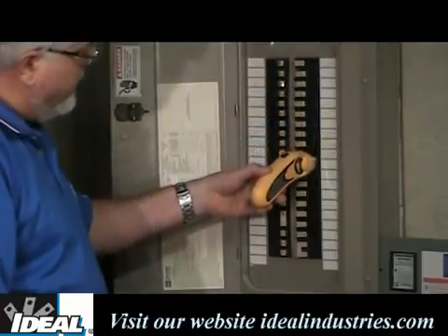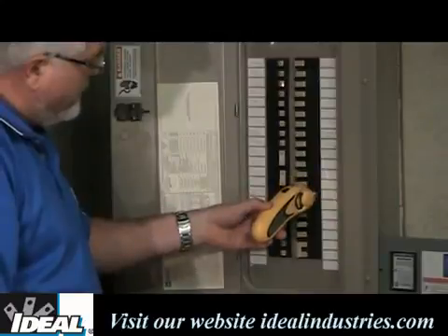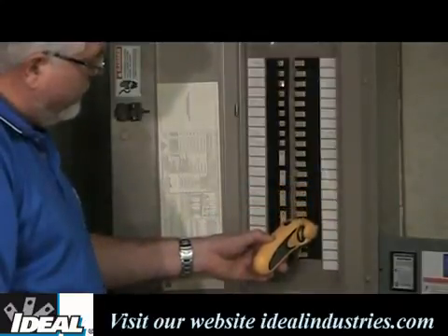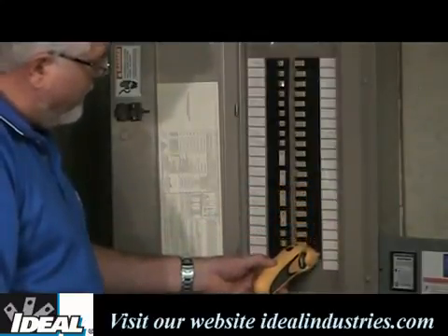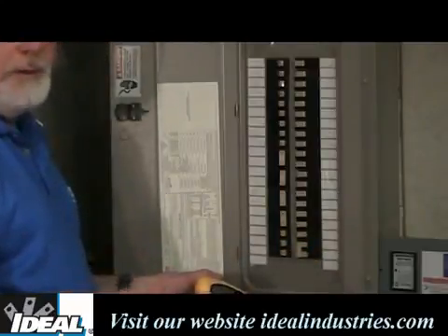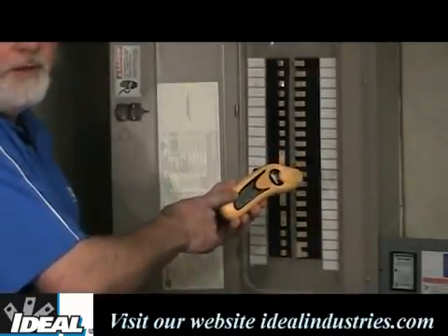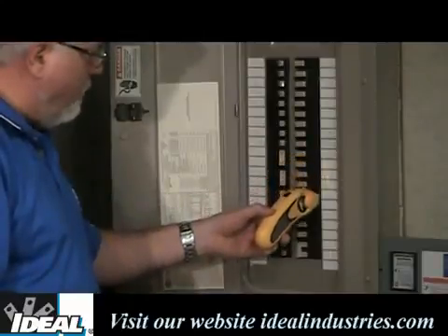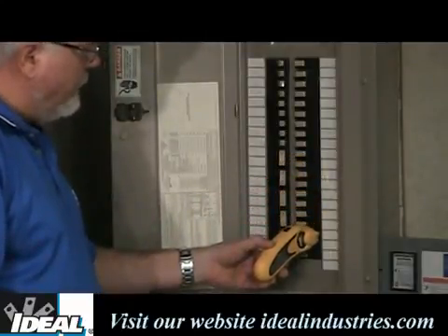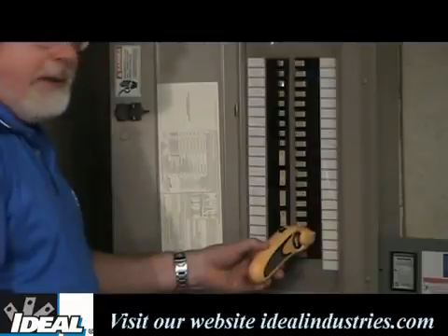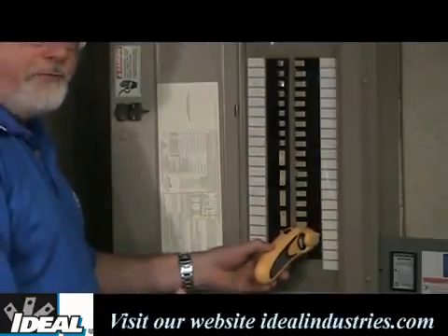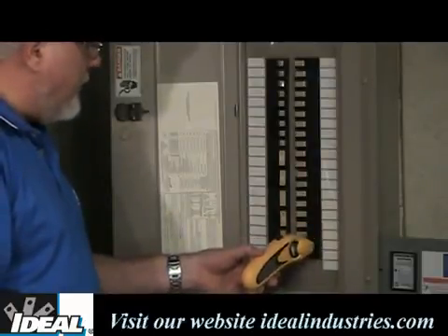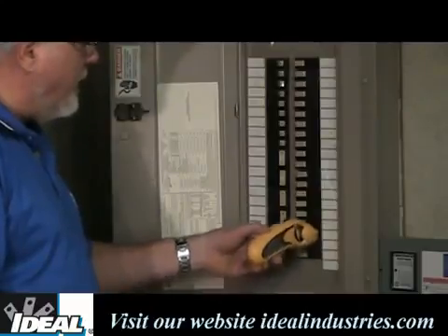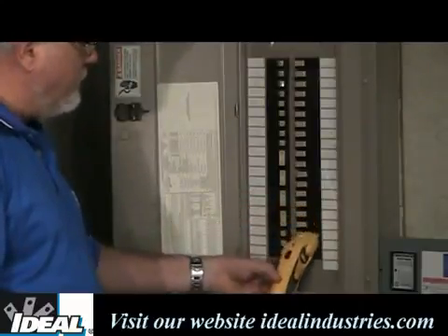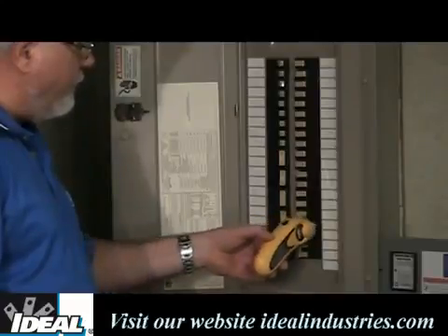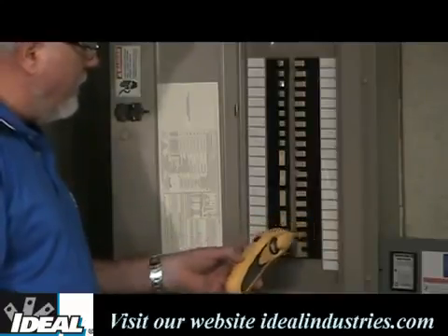Sooner or later it should start beeping at me as I go through the panel. Oh, there it was. Okay, there it is. That was the only one that beeped, so I know that's the one the receiver unit found. If I go back over it again, holding it up to it, it continues to beep at me, and the little green light on the unit flashes, indicating that's the right breaker. Again, if you're at an odd angle, the unit won't beep at you, so make sure you're flush or even with the face of the breaker.